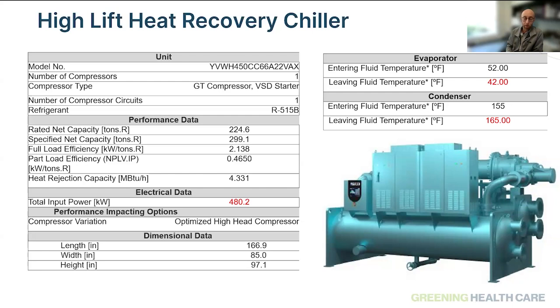But typically, most heat recovery machines shouldn't be designed for your full year summer cooling load. And I think the biggest message to deliver to any existing facility is, if you want to take advantage of heat recovery, the important thing to do is to study and analyze your current building loads throughout the entire year. You don't want to waste your time and resources properly sizing your heat recovery machine for what you think is the biggest cooling load that you're going to have. We can have auxiliary cooling machines that can serve that space.